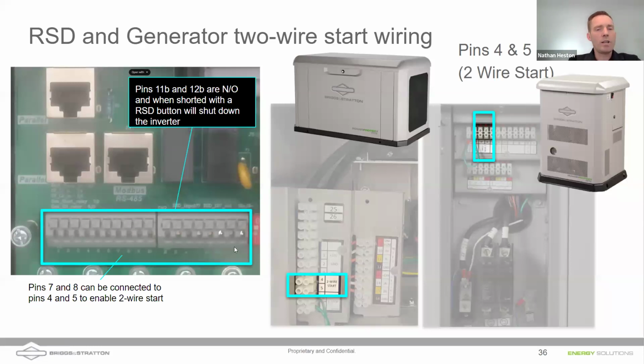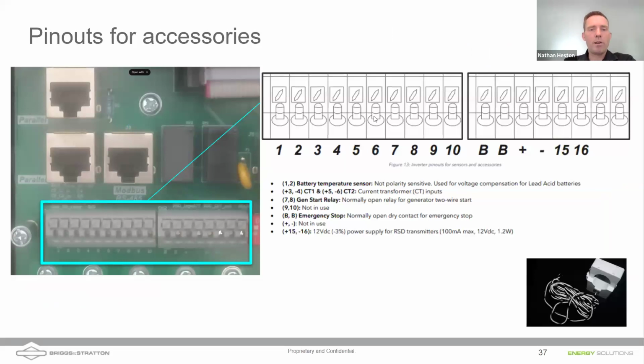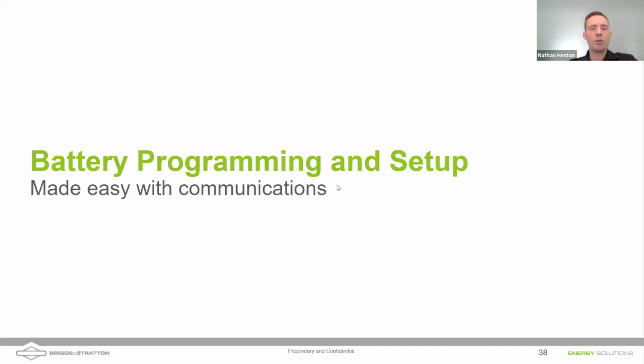The other connections that are here are for CTs. So if you want to monitor the power being drawn from the grid and offset that with batteries, you can do that. I don't remember which pins, or which connections here, are for the CTs, but you can wire these CTs into the smaller pinout. And I do have the reference for you on the screen as to what these pinouts are. You can also find this, of course, in the manual. So CTs are being shown on the right side of the screen there. And again, the CTs are on the screen there, pins 3 and 4 and 5 and 6. You do have to pay attention to the direction, the orientation of the CTs as well. So if you're installing CTs, make sure you use that arrow, and you'll either have to point it to the grid or away from the grid, depending on the type of connection that you're making.